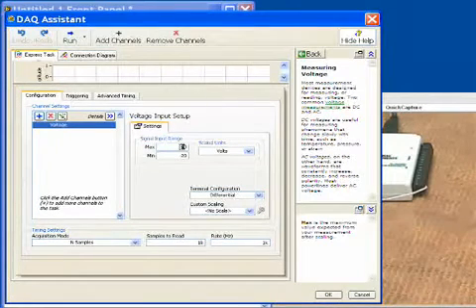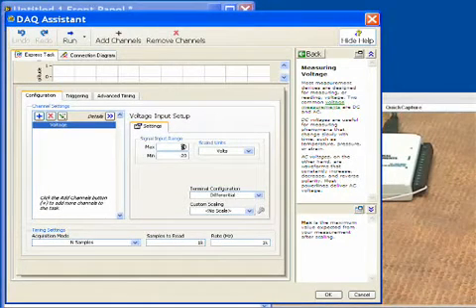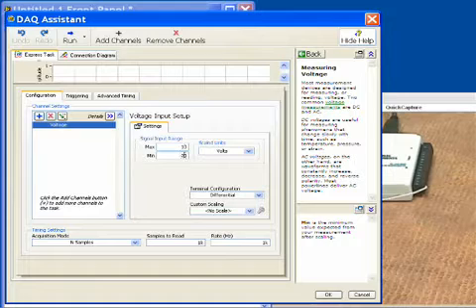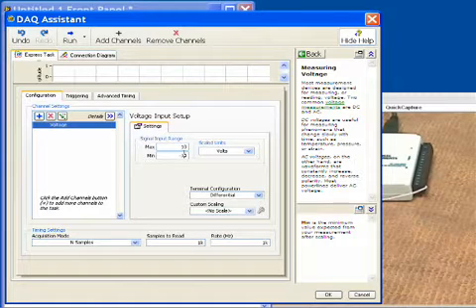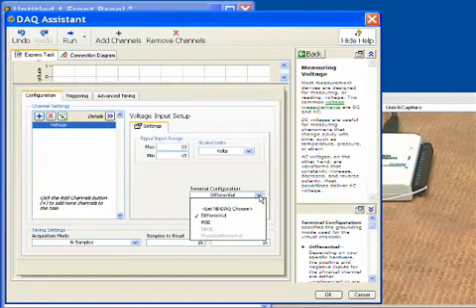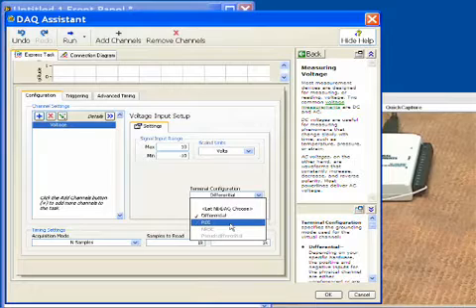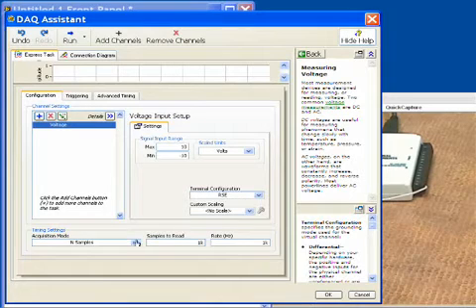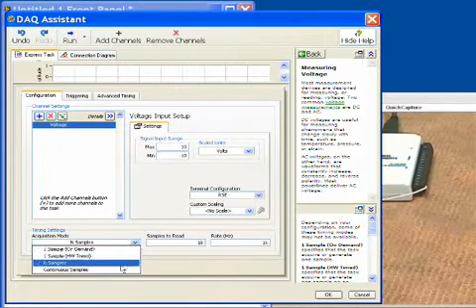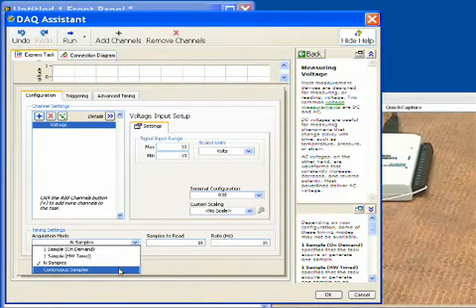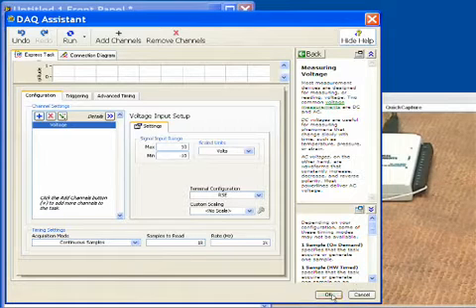Next, we'll set up some parameters for this acquisition. Our device can go between plus and minus 10 volts, so we'll specify that right here. Next, we want to set the terminal configuration to be referenced, single-ended. And then finally, we want to do continuous samples, which simply means there'll be no gaps between our data.